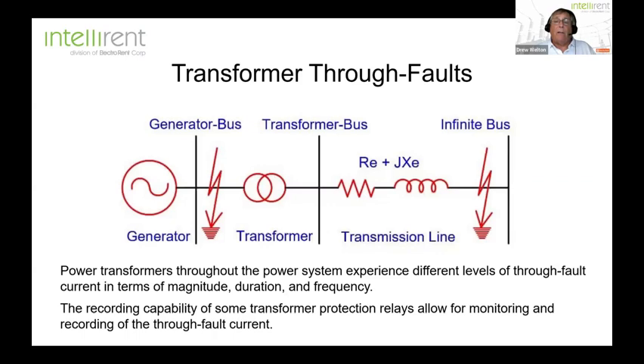So, what is a through fault? Well, that's when the transformer experiences current flowing through the primary and the secondary windings equally because you've had a fault either on the line or on the bus where the transformer is connected. Now, this will not cause your protective relays, especially your differential, to trip because the current's equal going through. It's just a much higher value. Back in the days when they first published standards for transformers, the big thing was thermal limits. Okay, and that's basically a guide as to how much thermal capability a transformer would have. Well, soon after that, they discovered that it's going to be important for us to look at transients. What kind of transients can it stand in terms of multiples of base current rating?